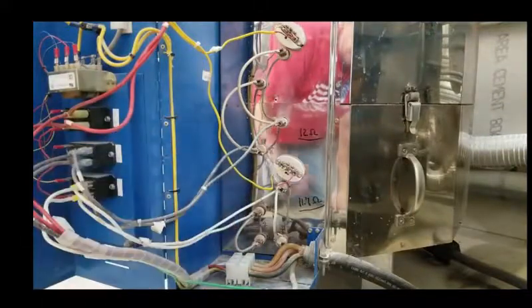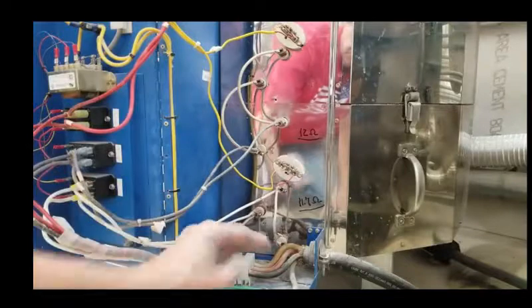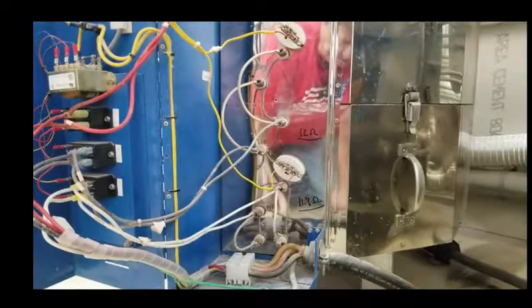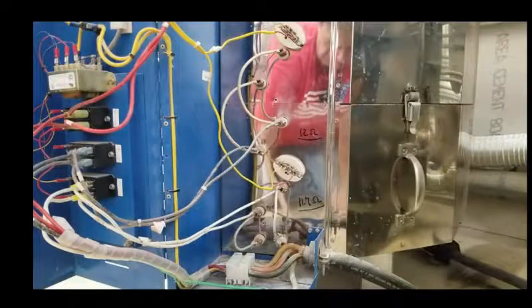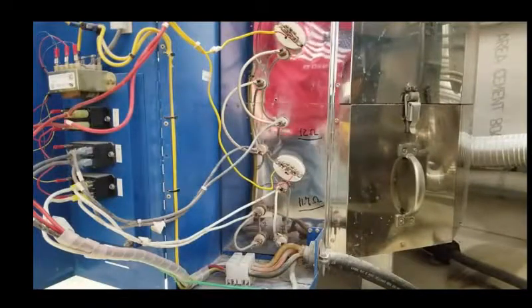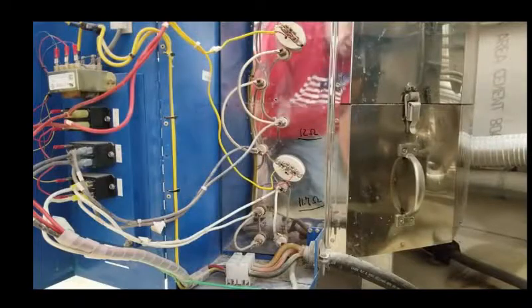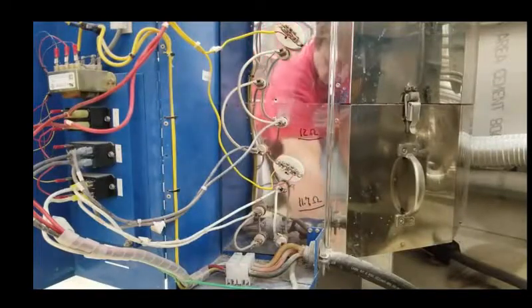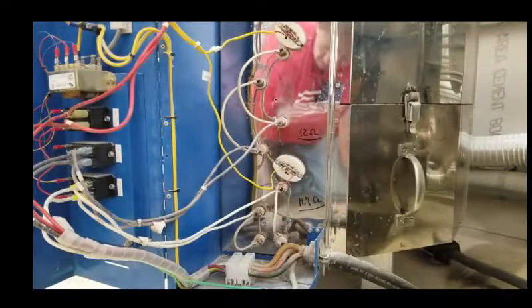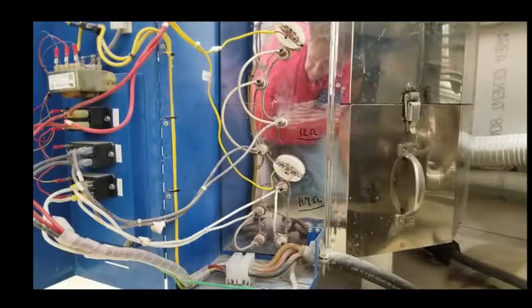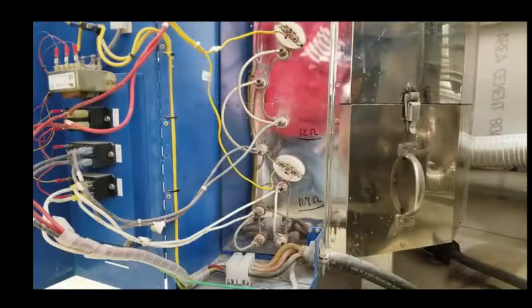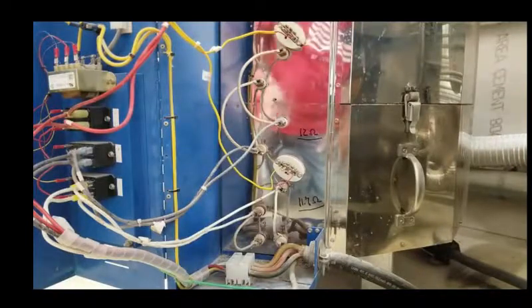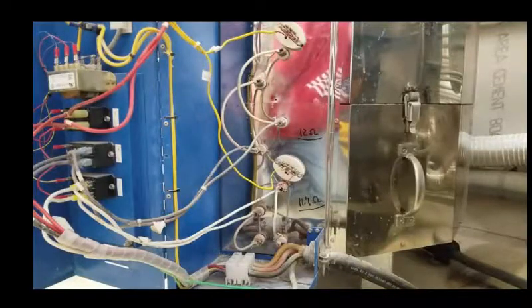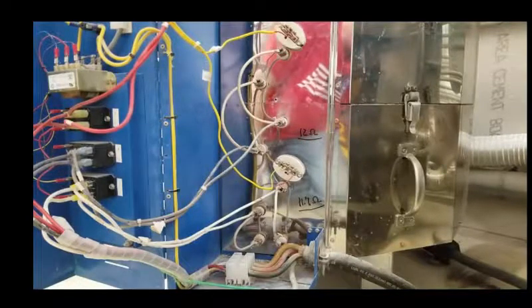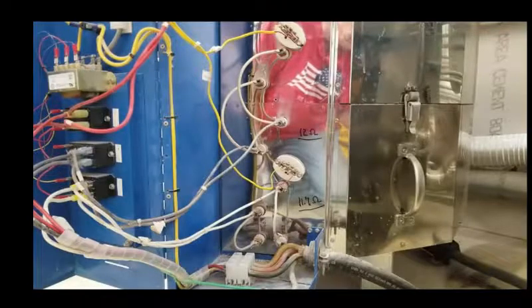So now we took this piece out, got a nice new piece of MG wire, which is rated at 450 degrees C, which is probably the hottest wire you can buy. I keep a supply of it just for this, and we will fire this all up again and double check that connection. But it's a good thing we did a nice full thorough checkup, because that connection was wasting power heating up and probably going to damage our relays as well. So back in a second, we'll do some temperature measurements just to make sure we're done.